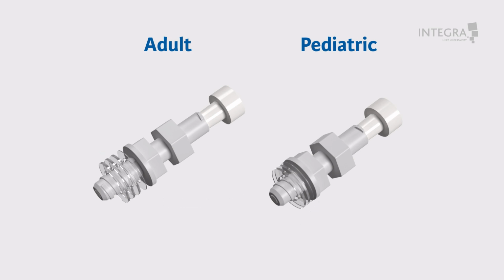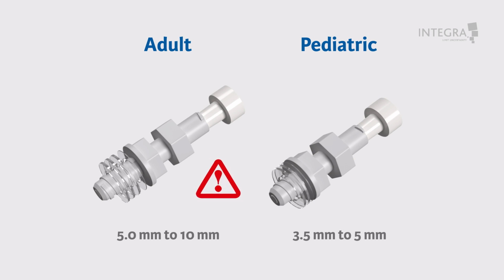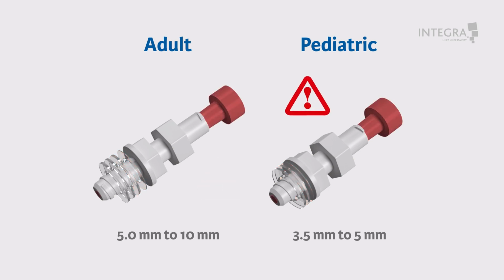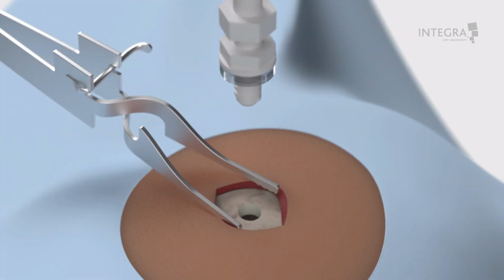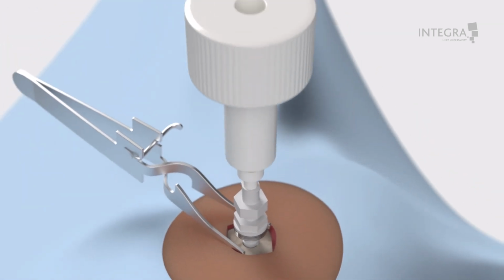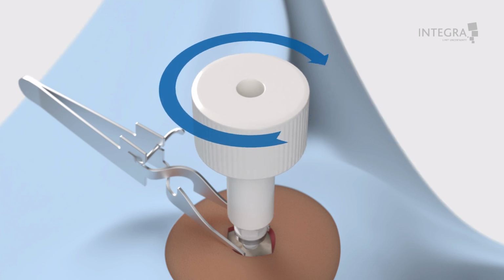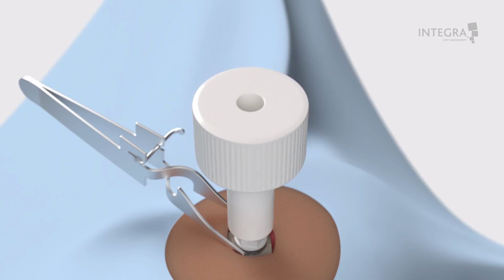The range of adjustment available to the surgeon is adult 5.0 mm to 10 mm, pediatric 3.5 mm to 5 mm. Warning: do not remove the thrust washer and sealing washer that are pre-assembled on the skull bolt, as this can result in a fracture of the device or in an inadequate seal between the washer and the skull. Note: do not remove the obturator from the skull bolt. Put the plastic skull bolt into position and place the screw handle on top of the bolt. Turn the screw handle clockwise manually into the prepared drill hole until the spacing washer beneath the screw flange rests close against the outer table of the skull.